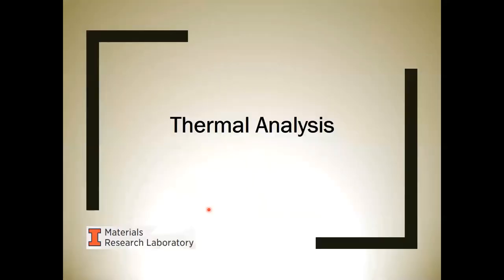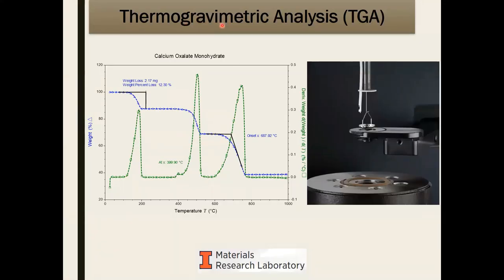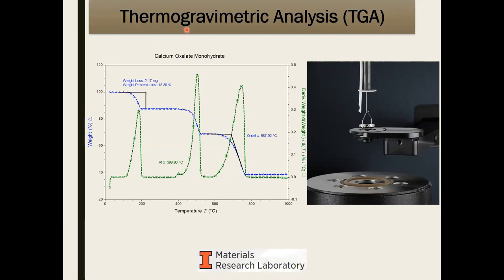The next group of techniques is thermal analysis, where we use heat to investigate different properties of our material. The first technique is thermogravimetric analysis, or TGA. Breaking down the word: 'thermal' means heat-based; 'gravy' sounds like gravity, which affects how much things weigh. So if we measure how much things weigh at different temperatures, we are doing TGA. The instrument has a thermocouple for temperature measurement; the sample sits on a pan, and below is a furnace that moves up to encapsulate the sample. As temperature increases, the sample pulls on a thin metal wire, tilting a balance, and we continuously measure mass.